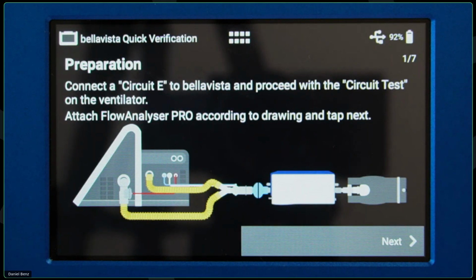So in this case here, for my quick verification on the Bella Vista ventilator, it asks me to set up the device as shown in this picture here. I can also see that here. And the nice thing is, sometimes in service manuals, you just have pictures with a different gas flow analyzer, probably a different brand than the one you're using. And here you can see it exactly for the device that you have in use.